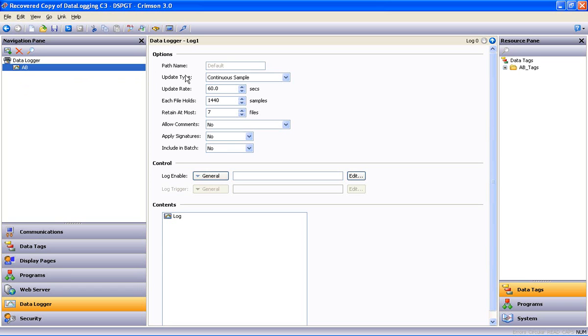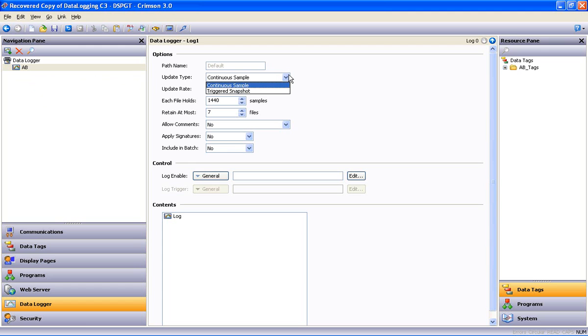Looking at the options for this log, you'll see two update types. You'll notice continuous sample, which allows the user to program the rate at which the samples update, or triggered snapshot, whereby you specify an event or condition that causes the logged update on each occurrence of the event or condition. We will use continuous sample.